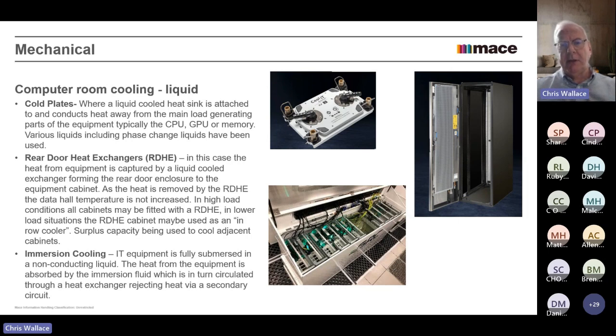And if you go back a couple of slides ago, where I said that the chip can run happily up to 105°C, if you pump a liquid through that, in most places in the world you'd probably be able to throw the heat onto the roof and ditch it with a dry cooler rather than using a cooling tower. And you won't need any chiller. Even in most of this part of the world, the average summer design day temperature would probably be not much north of 40°C. And if you're running liquid in the 70s or 80s, you should still be able to ditch that through a dry cooler.